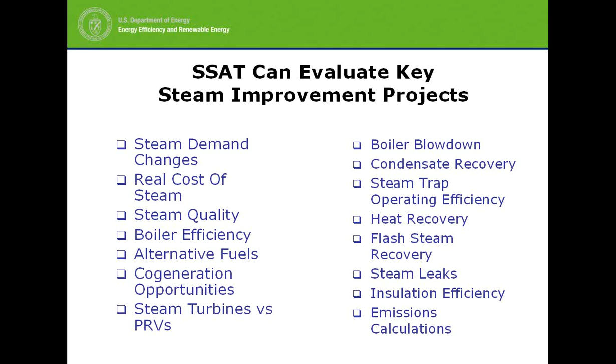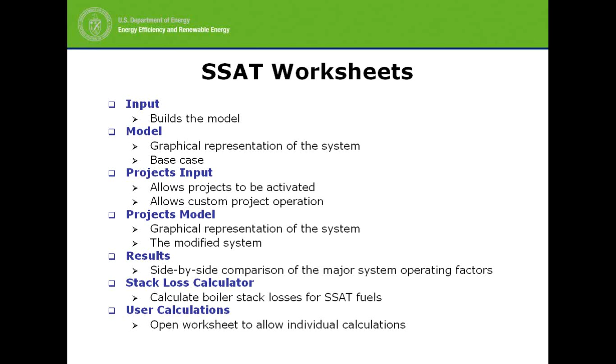It's in Excel, so you've got worksheets - an input page, a model page. You can input projects and do what-if evaluations, and it will show you what the new system will look like in the project's model. Results is where the rubber meets the road - that's the key page you'll always refer to when doing what-if analysis. There are also good tools including a stack loss calculator for calculating boiler efficiency using stack loss information, and a user calculation page to store data you collect during the assessment. Everything is captured in one file: raw data, model, and results.